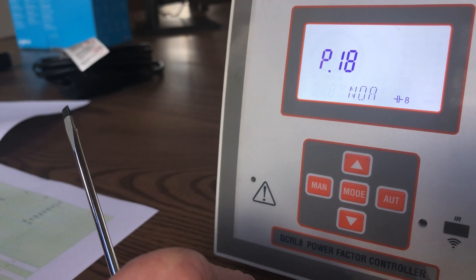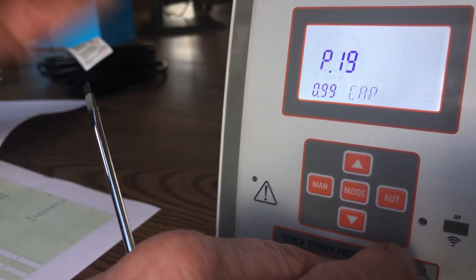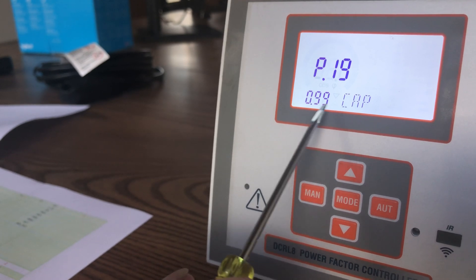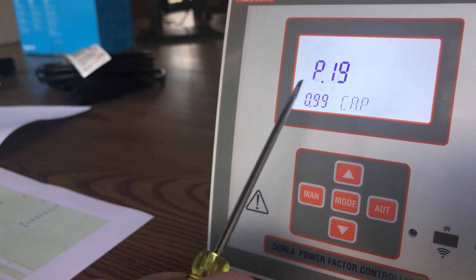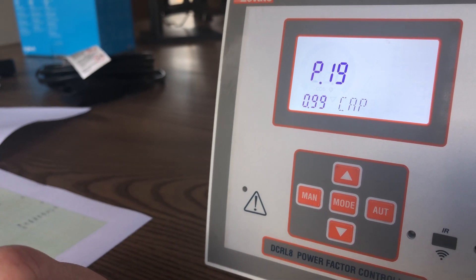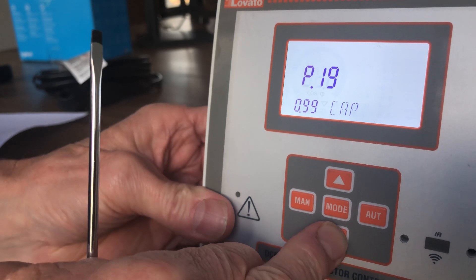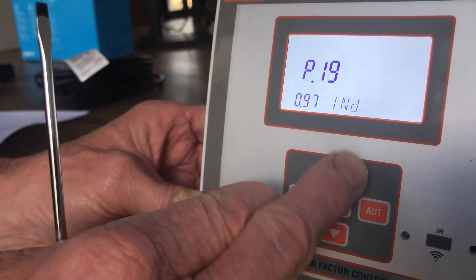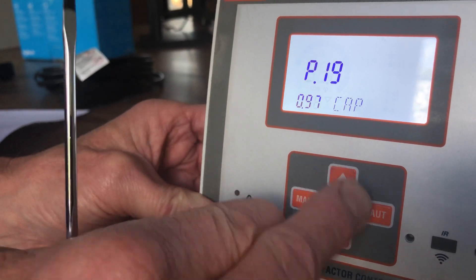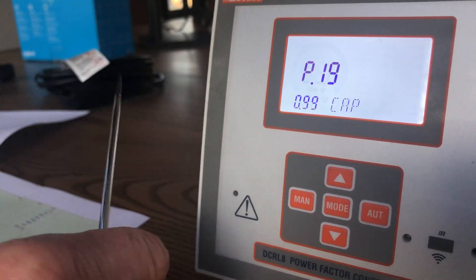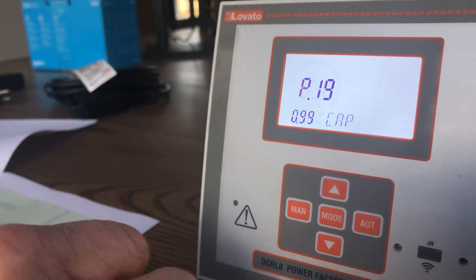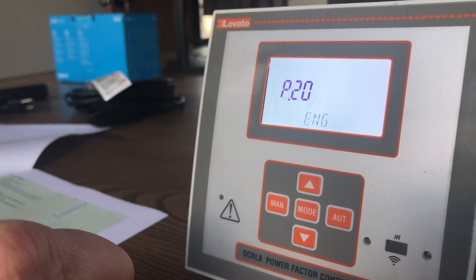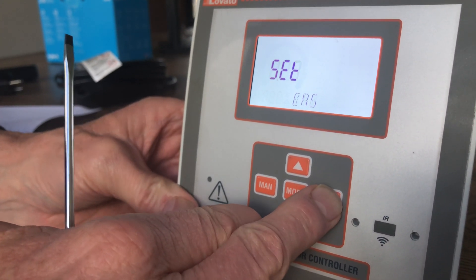P19 is your target value for your cosine — typically we put 0.99 capacitive, because it seems to work better in terms of utilizing your available steps. You can change that to unity, inductive, 0.99 the other way, or capacitive — most often we'll set it for 0.99 capacitive. The next setting is the language you're going to use — in this case we're using English. Hit it one more time and you're back to BAS — basic.